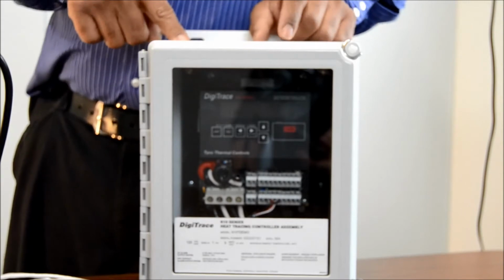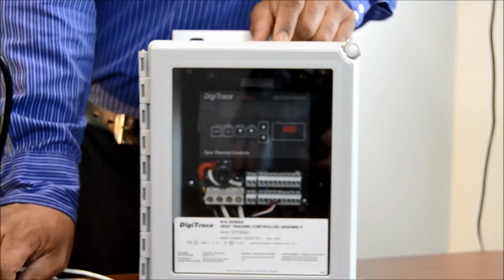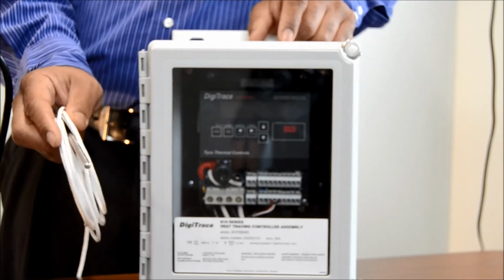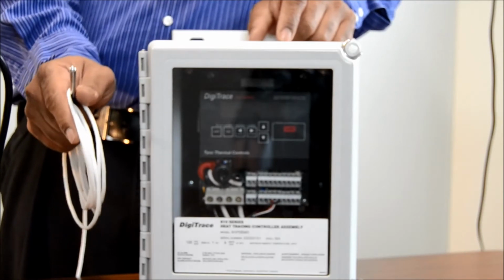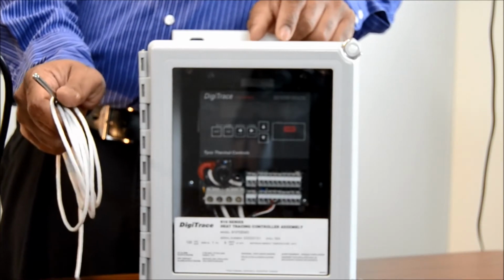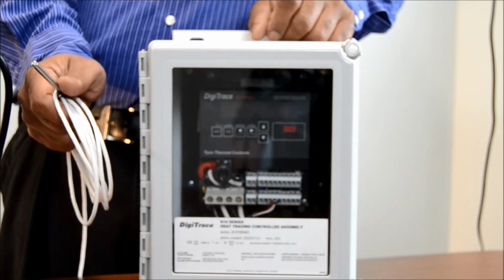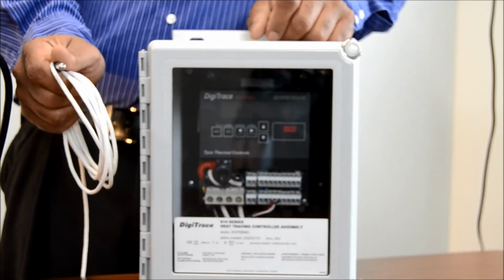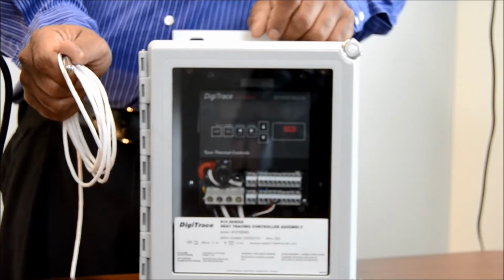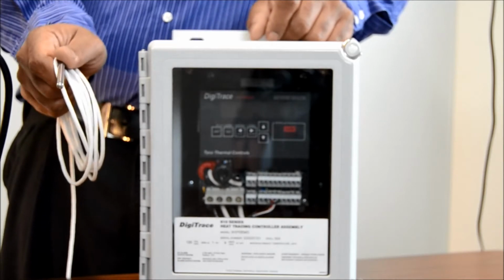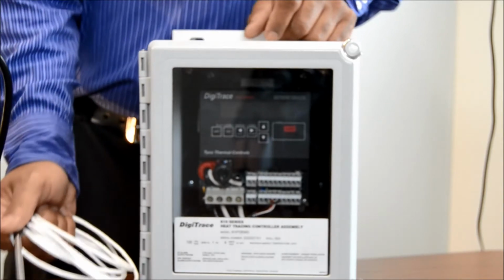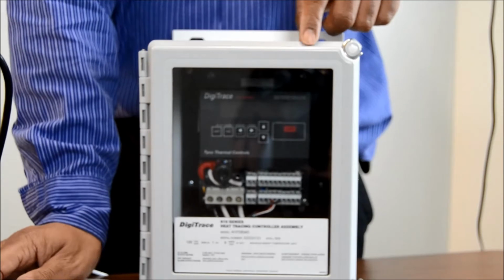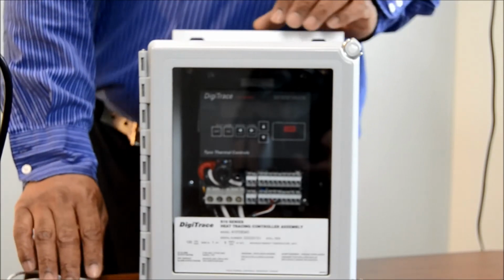Out of the 910 controller, you also have a sensor, which is an RTD. There are two types of RTDs. One is an ambient sensing RTD that senses the air temperature, and the second is like this right here, a line sensing RTD, which goes on the actual pipe itself. You connect it to the terminals in here, and we'll discuss that a little later.